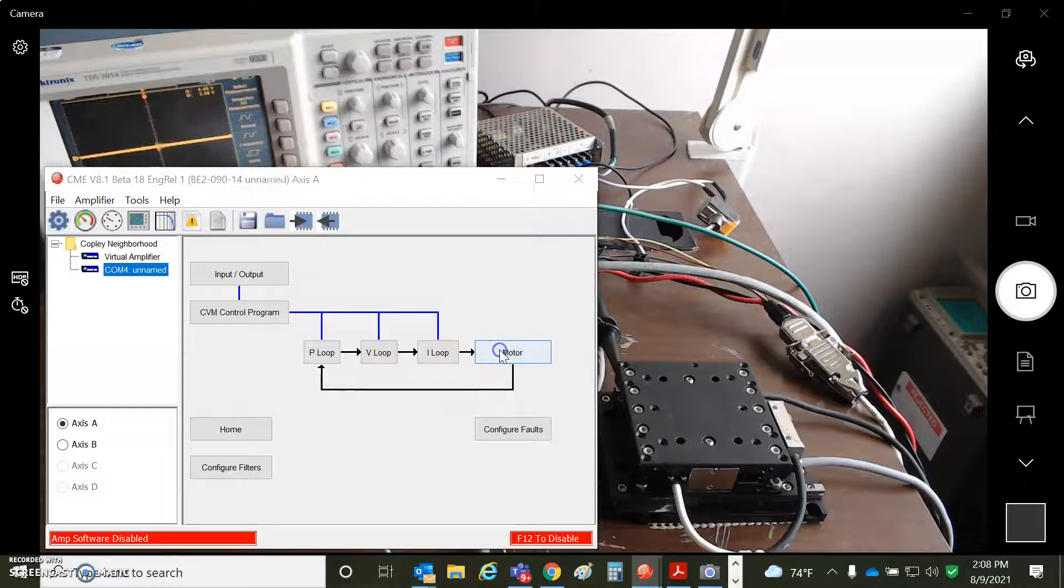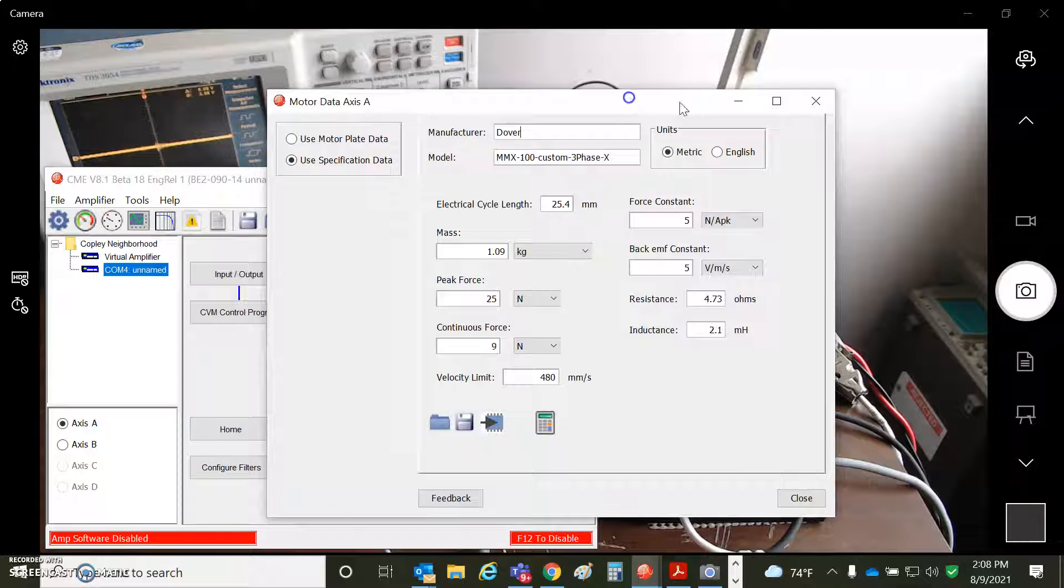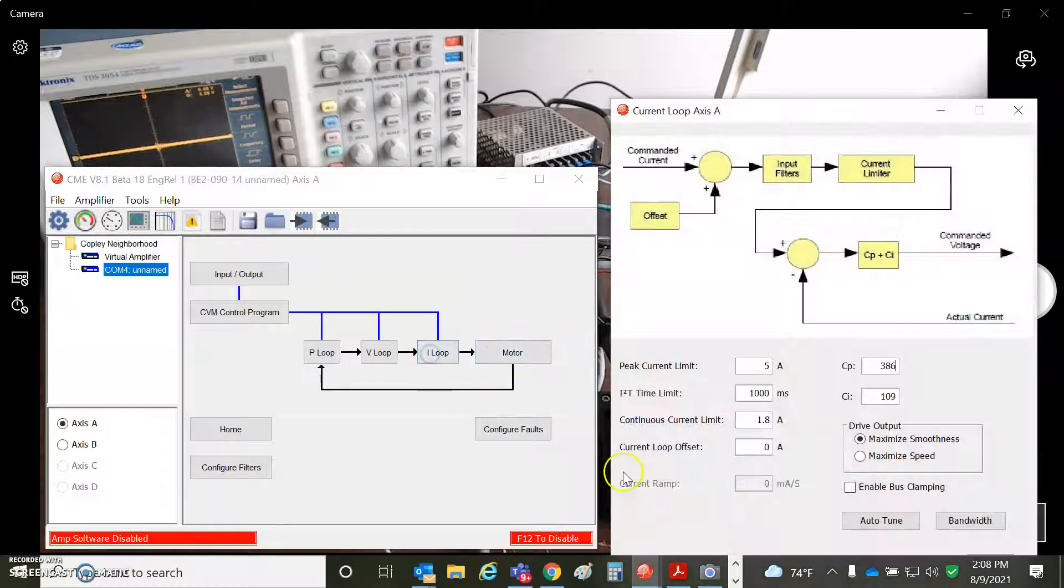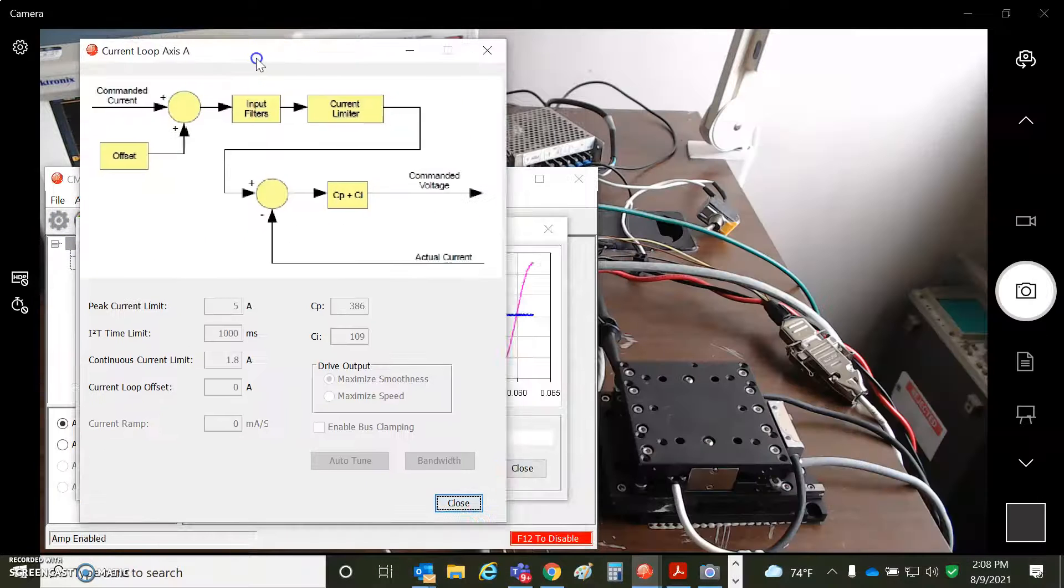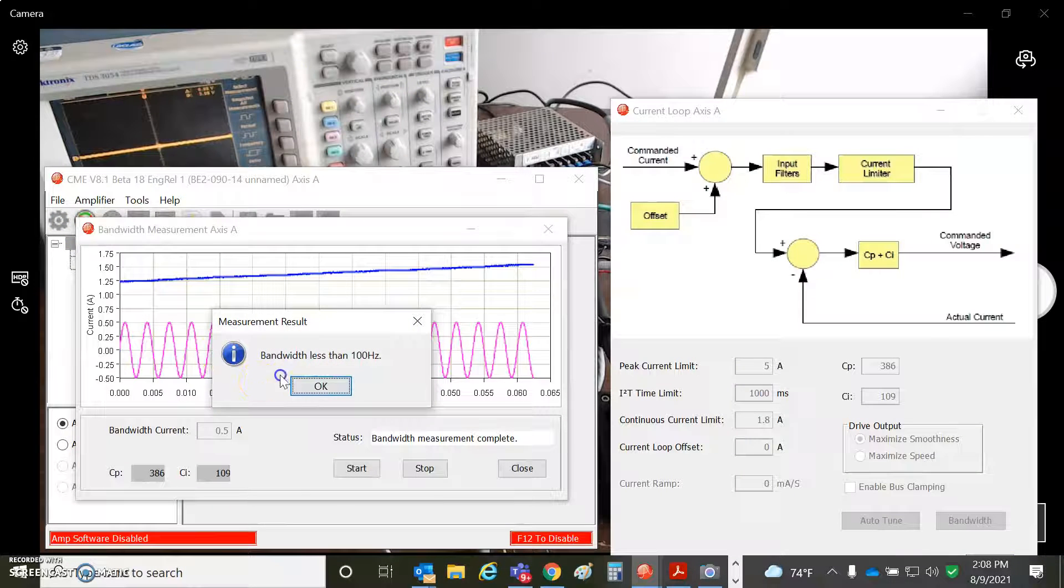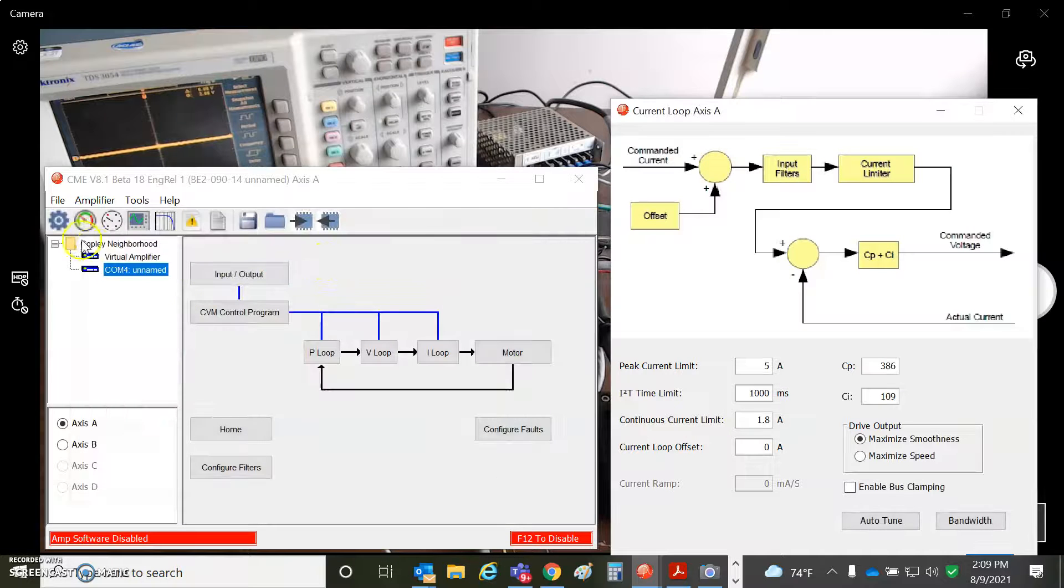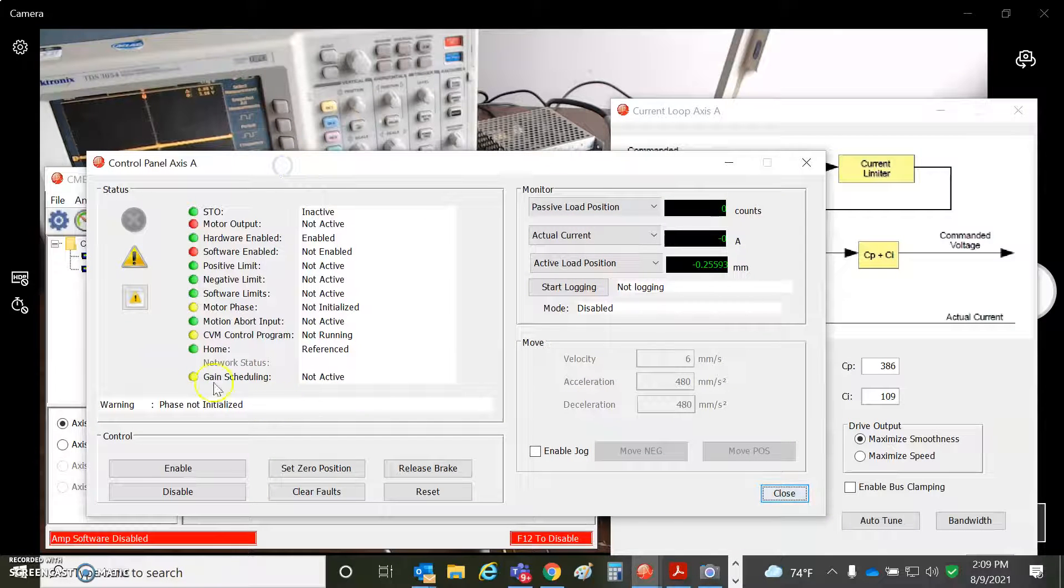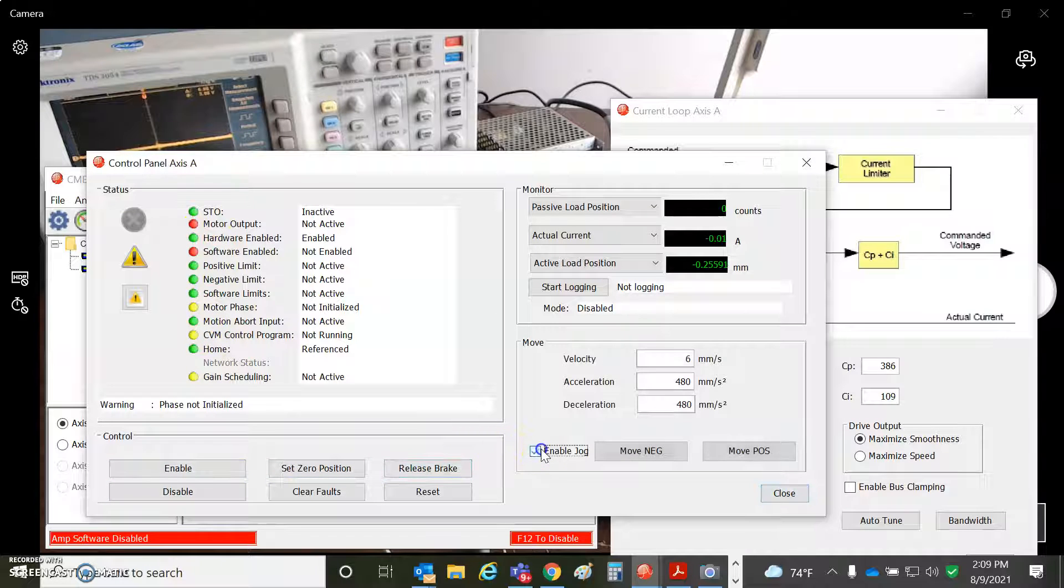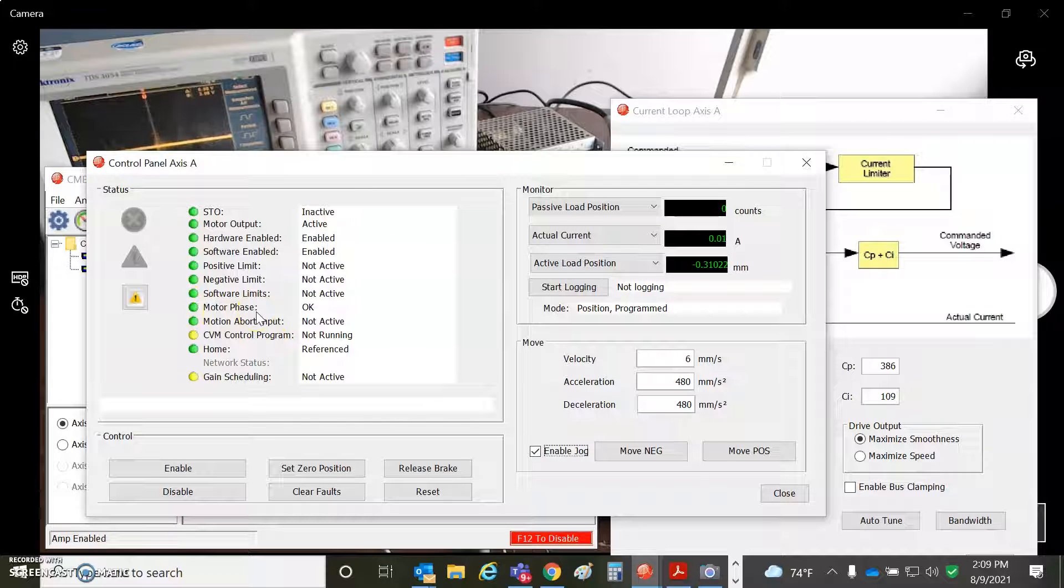So we'll take a look at we entered the data for the motor here. And we hit calculate. And that produced some current loop tuning. So we can see, ah, we have to phase first. Sorry, it just jumped right in and started tuning. It was not phased. You see, not phase. So I have to enable it.